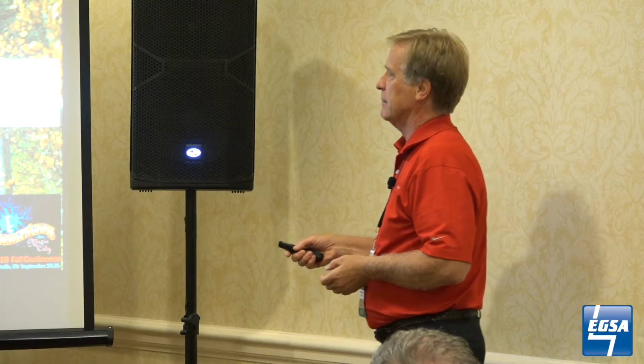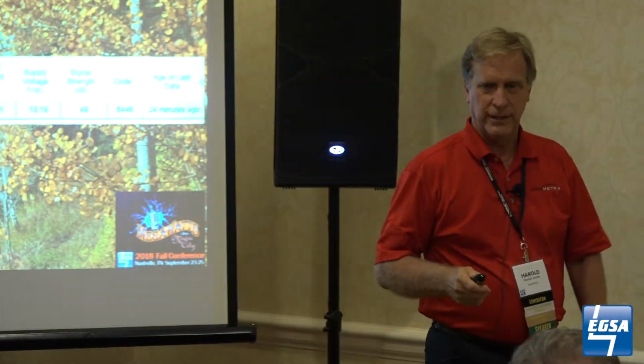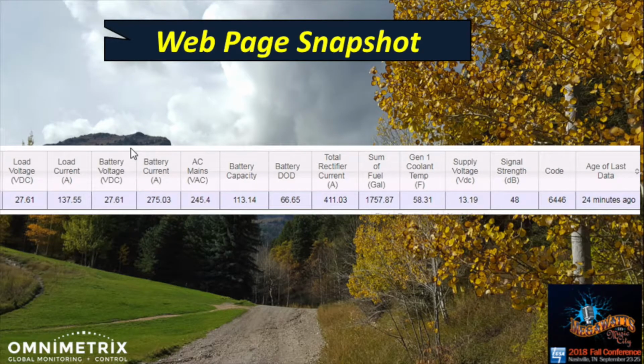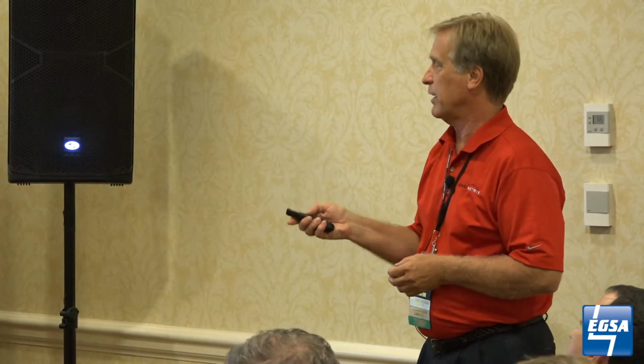Another important item for this one - you'd think, why do I care about coolant temperature? Well, the reality is it's on top of a very frozen mountain. Even though it's a propane-driven machine, you can't run a block heater 24 hours a day in a site like this - you'd have to put up much more solar to do that. So when the generator is needed, they have to turn on the block heaters to get the block warmed up enough to comfortably start. And then there's this other thing - the propane, when it's really, really cold, doesn't vaporize properly, so it required warming up a vaporizer subsystem in order to let the machine run. So coolant temperature is an important part of this application, and it's one of the more complicated parts as it turns out.